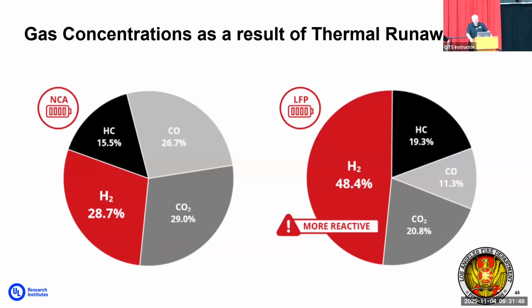If we go to a lithium iron phosphate type battery, you'll notice almost 50% of the gas that comes out when it goes into thermal runaway is hydrogen. Remember the Hindenburg - very flammable, very combustible. We have another 20% that's a combination of other hydrocarbons that can burn, 11% carbon monoxide, and about 20% carbon dioxide.